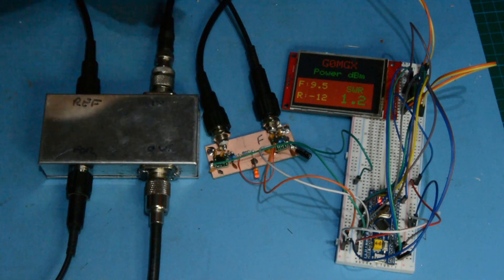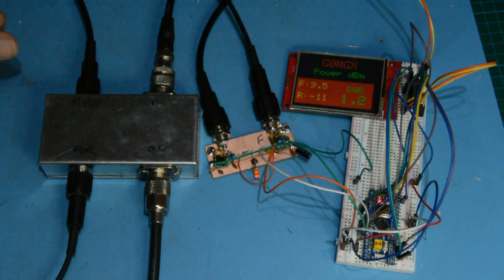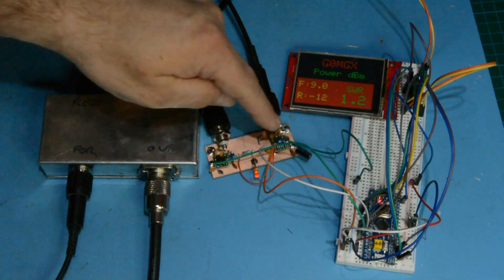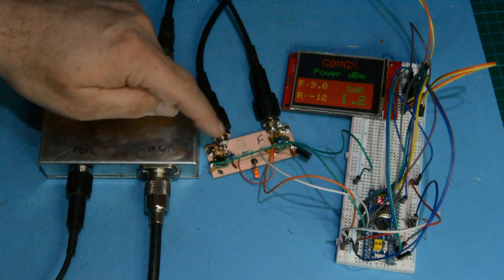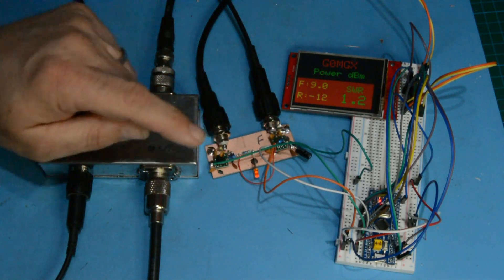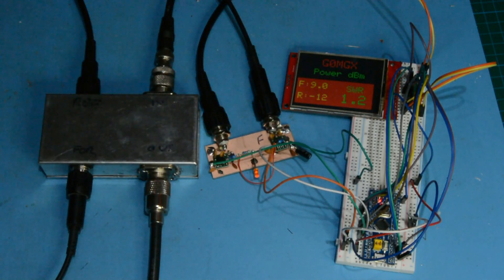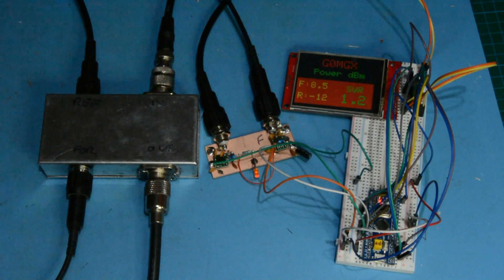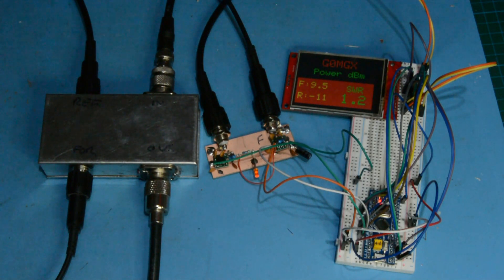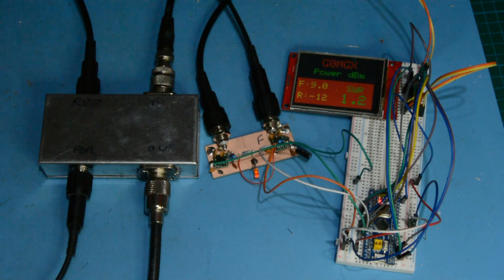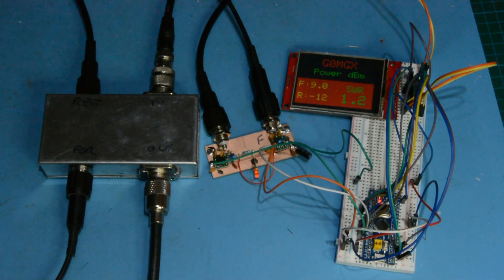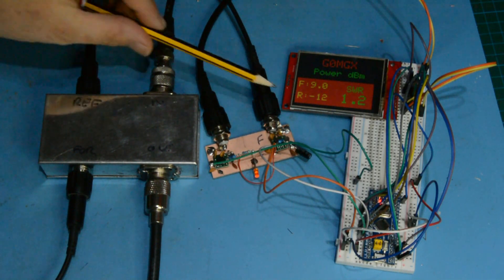The software, as I explained, is taking 100 samples of each of the ADC converters, so of the forward power and the reflected power. It's taking those samples every 10 milliseconds. Actually the code is designed to run and pull a sample in every 10 milliseconds, then every two seconds it does the calculation of the value. You can see that the screen is updating every two seconds.